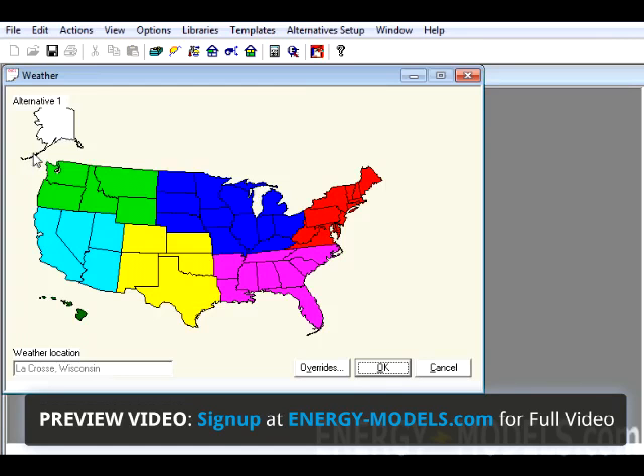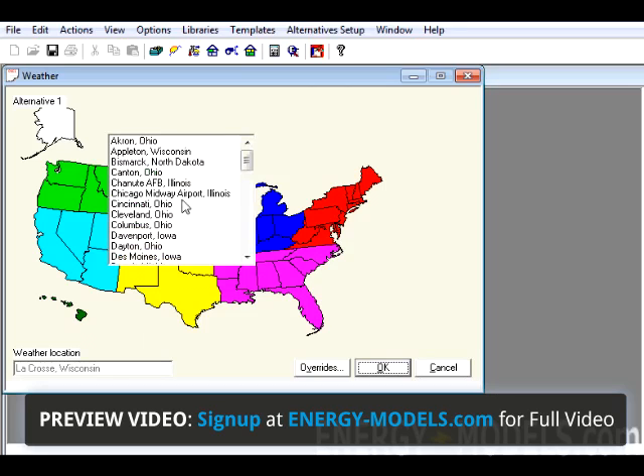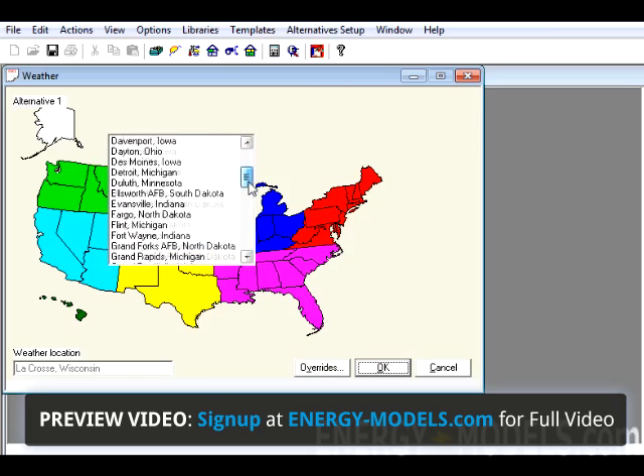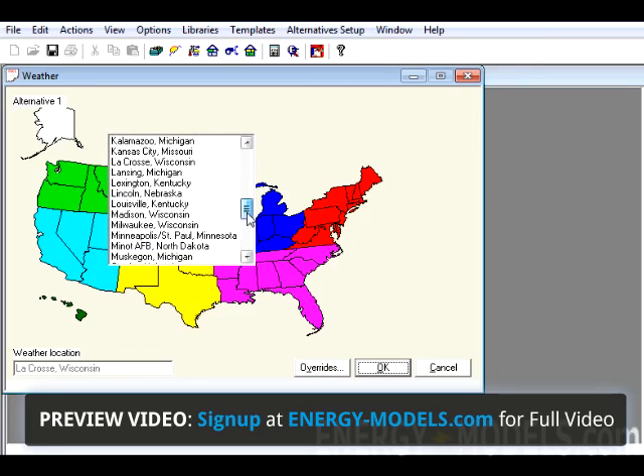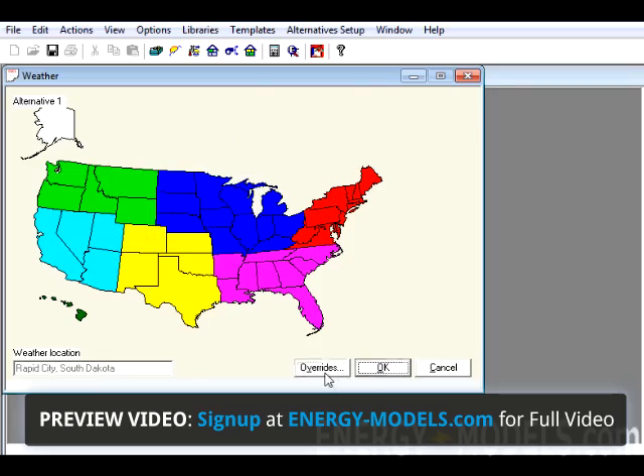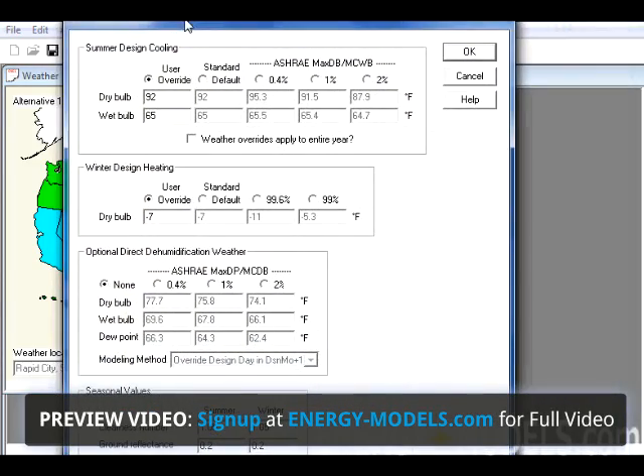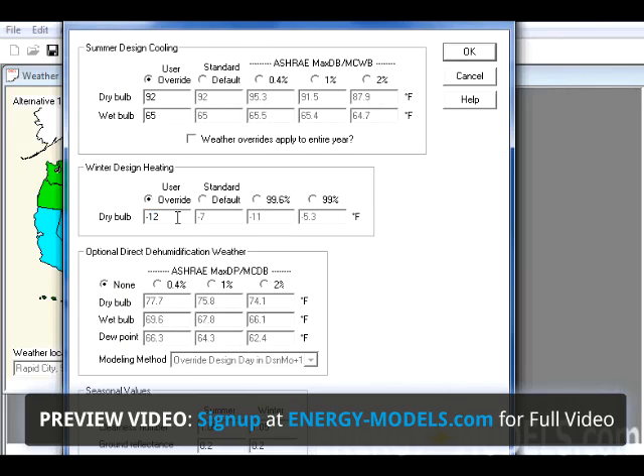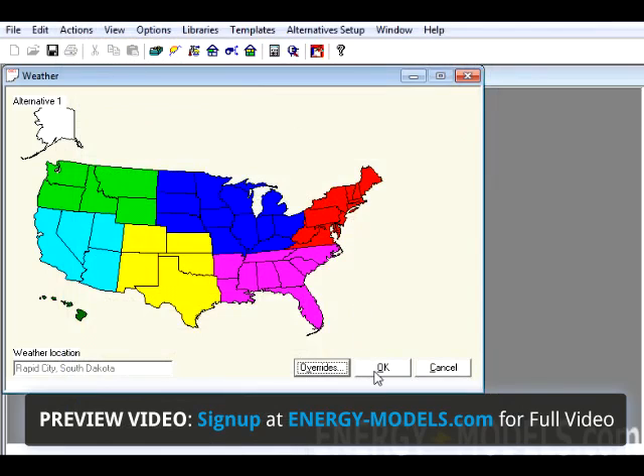Then we're going to select the weather information. In this case, we're going to select Rapid City, South Dakota, and click the Overrides button. We're going to select Minus 12 as the user override for Winter Design Heating Dry Bulb. Then we select OK, and we can select OK again.